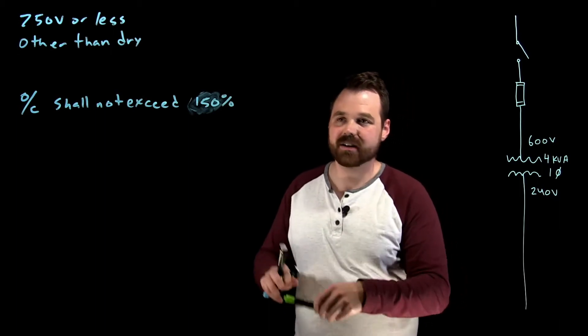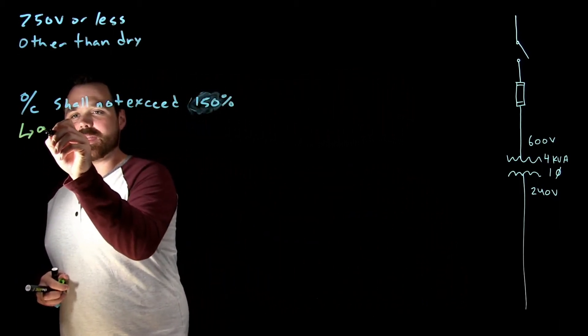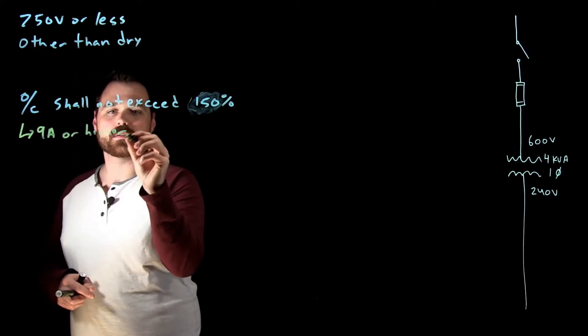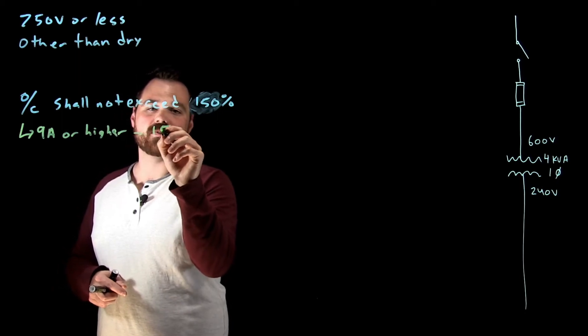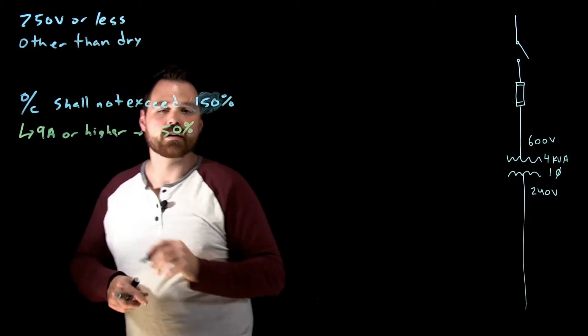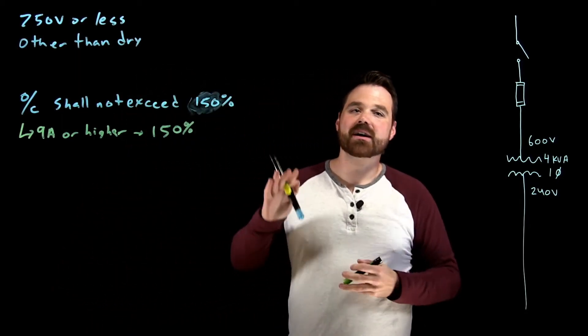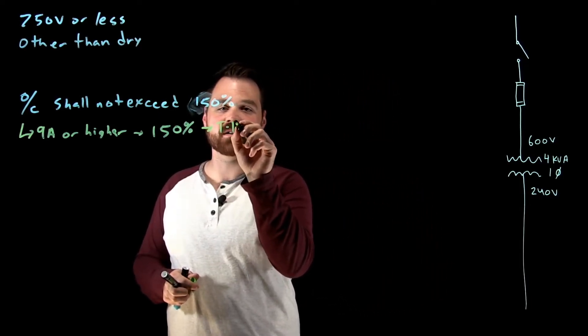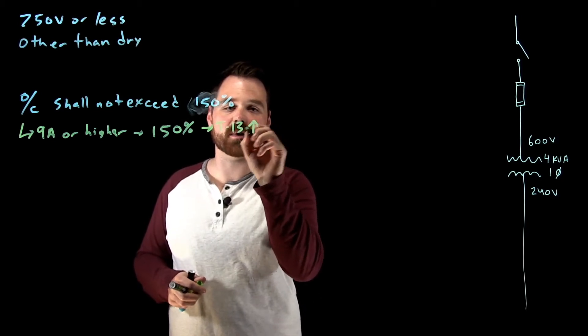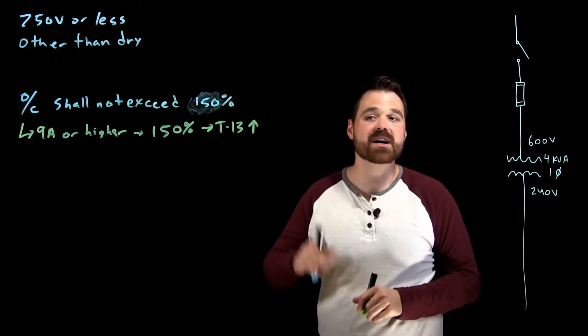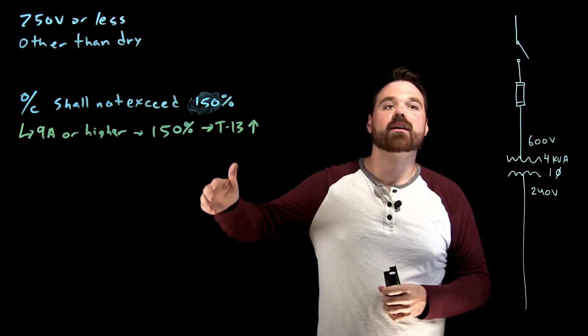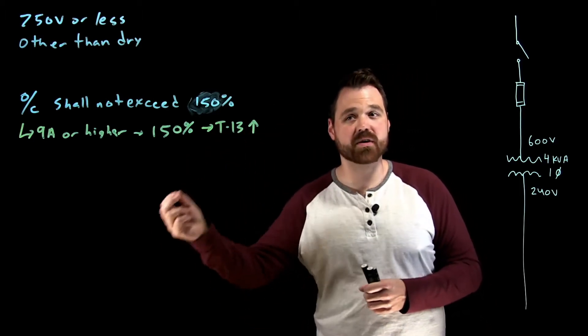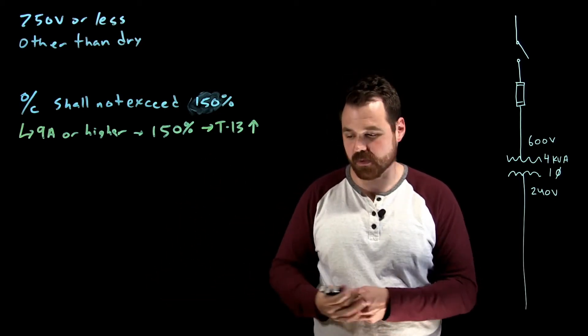Okay, if you are nine amps or higher, then it's 150% of the rated current. And if that's not available when you go to table 13, you are permitted to go up to a next higher size. So it says, if 150% of the rated current is not available as an overcurrent device, the next higher size shall be permitted.